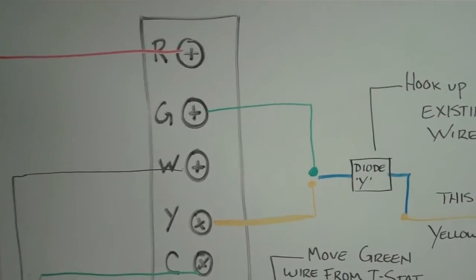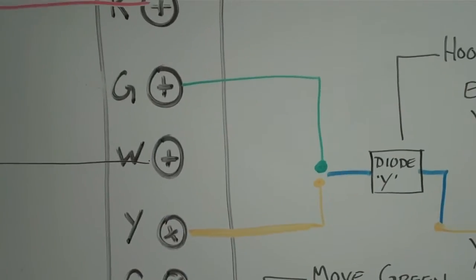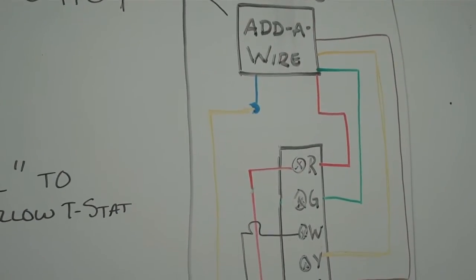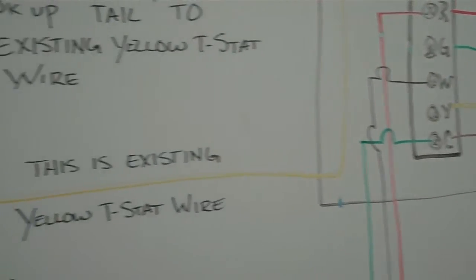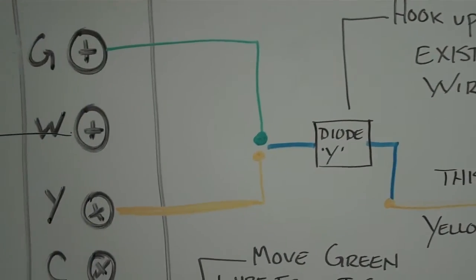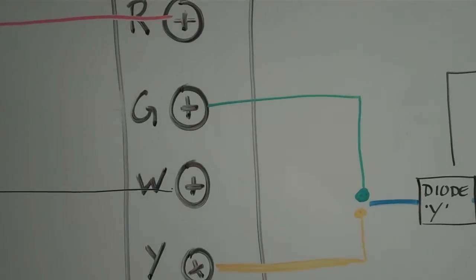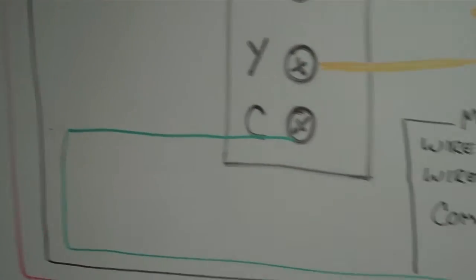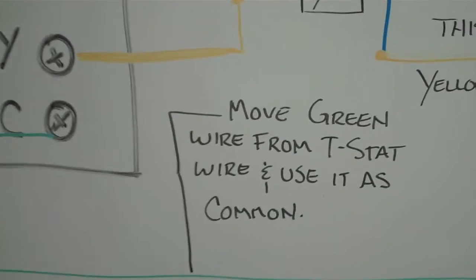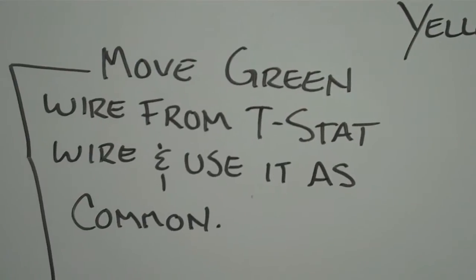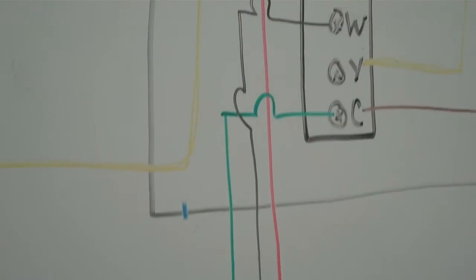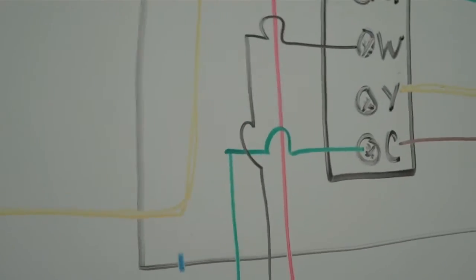So what we do is we remove the green and the yellow from the thermostat and we use the yellow to go back to the blue on the add-a-wire module. That goes back to that diode Y. The green we've taken off of this terminal I use to go down to the common. So now the green goes from the common on the thermostat. We just move the green wire from the T-stat wire and use it as the common. It goes all the way back and onto the common in the air handler.